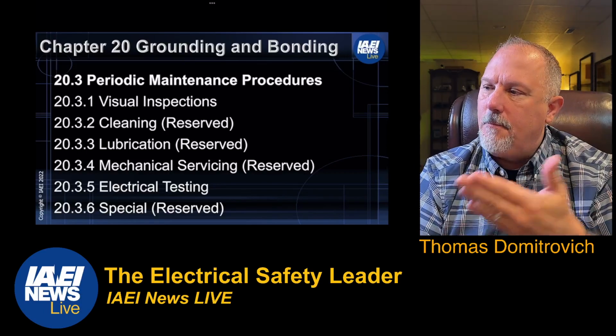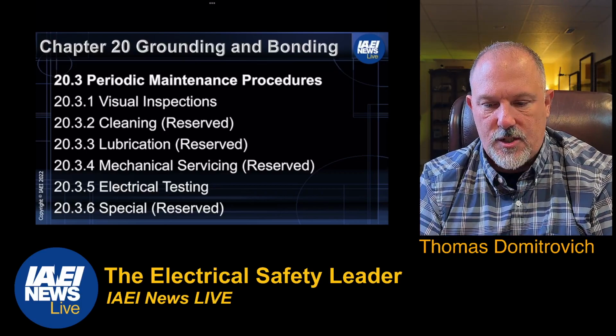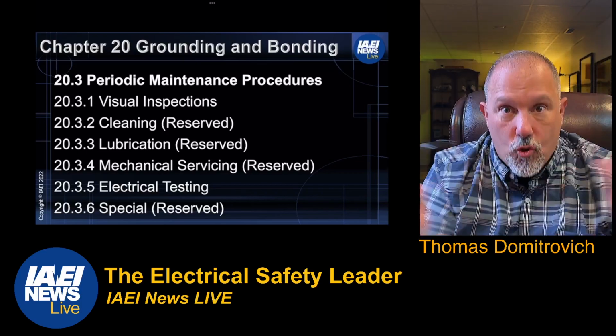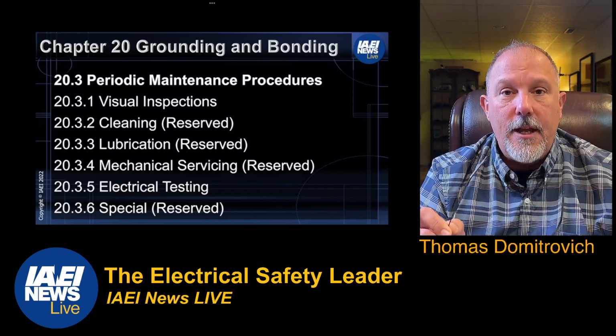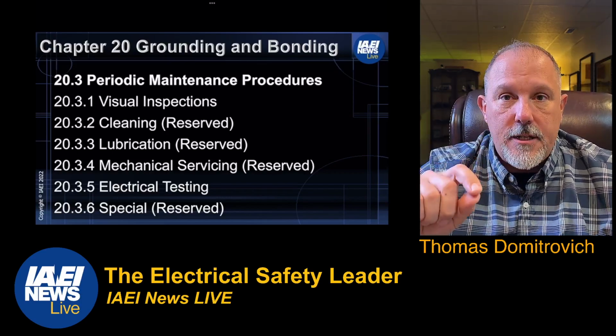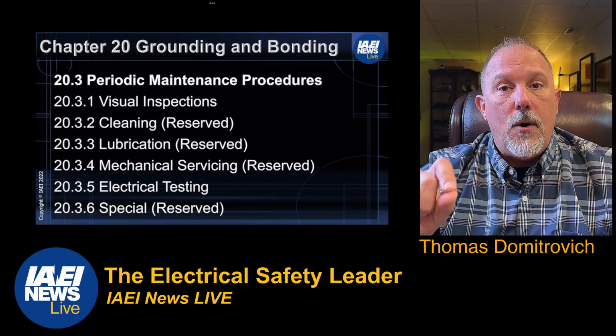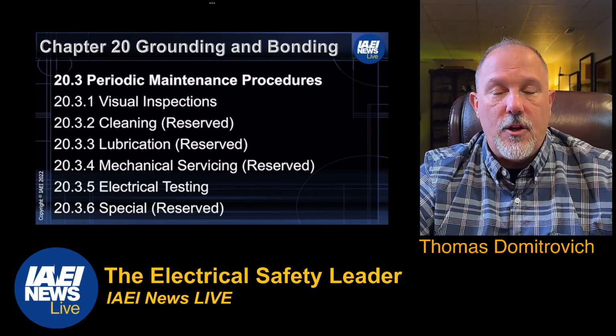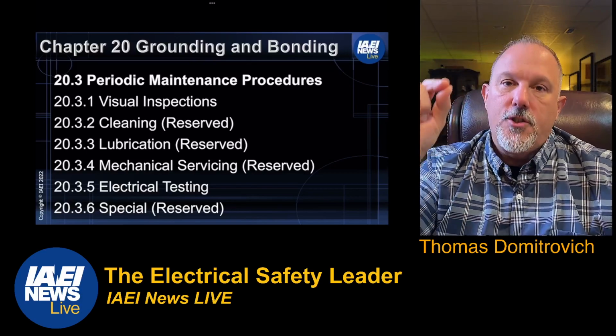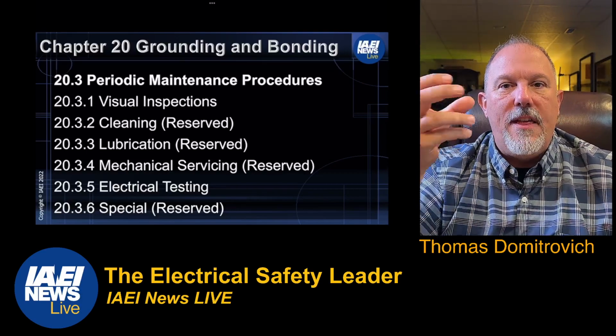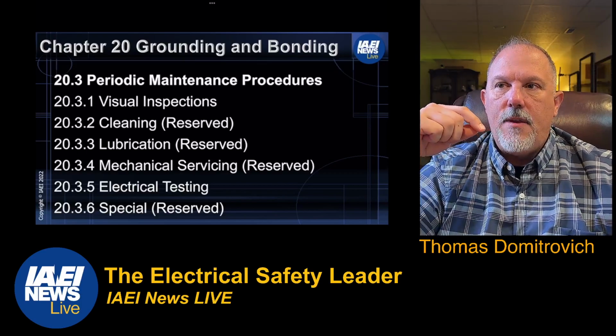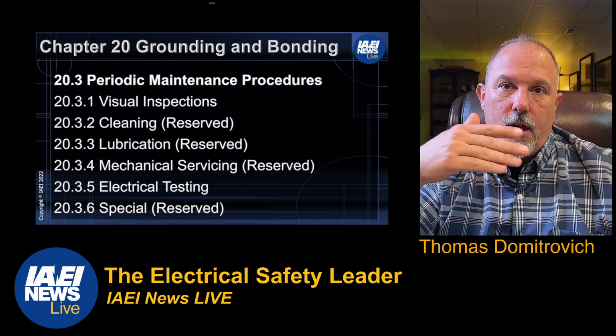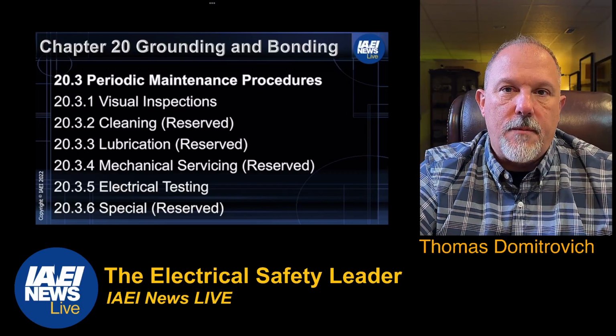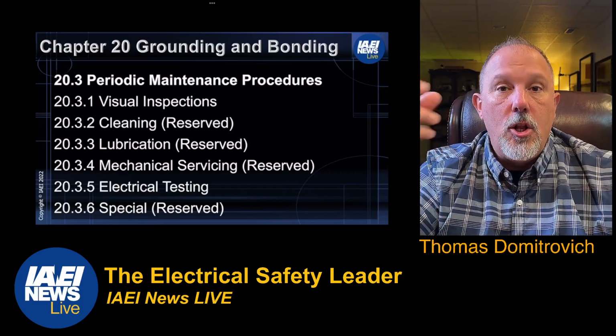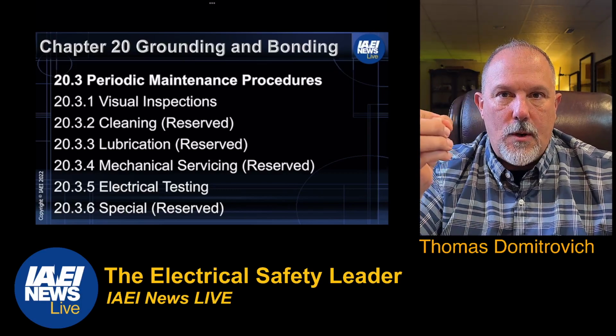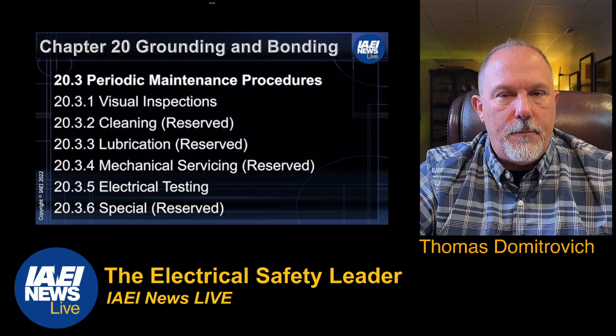So grounding and bonding is a discussion that goes across all of the different pieces of equipment. You've got to be very diligent in the details of how you bond to equipment. For example, if you have a powder coated piece of equipment, they may tell you to scrape off the powder coating to get the bare metal and then secure. They may tell you that if this is aluminum, you can't use a copper termination; you have to use something listed for aluminum equipment to create that bond. So terminations are very critical and important.